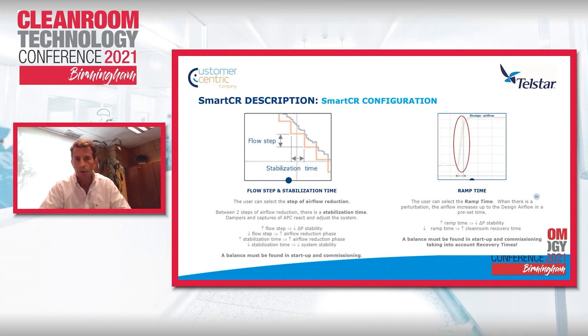So during the startup and commissioning, an important task, as I have said already several times, is to balance the right parameters, reaching the optimum ramp down time and minimum flow without compromising the four parameters: temperature, humidity, pressures, and particles. Same with the ramp up. If we increase the ramp up time, the pressure stability among the different rooms will decrease. If we decrease the ramp time, the clean room recovery will increase and will probably be a qualification issue.